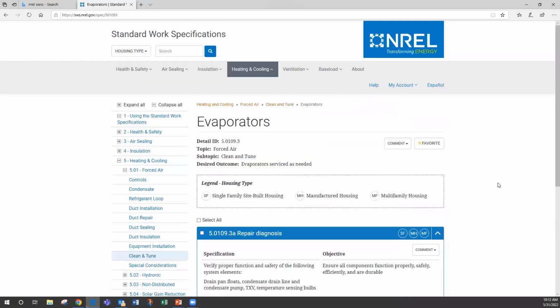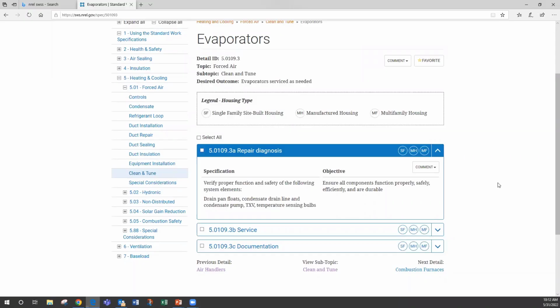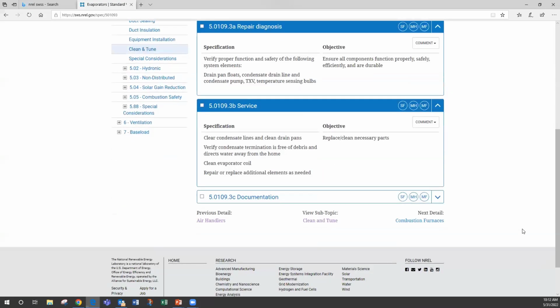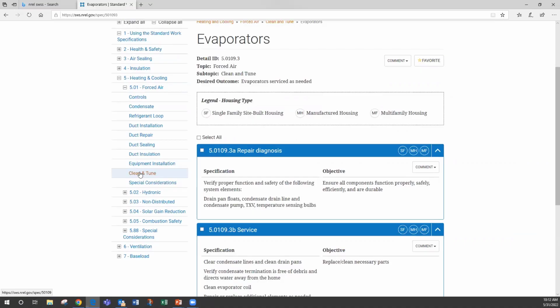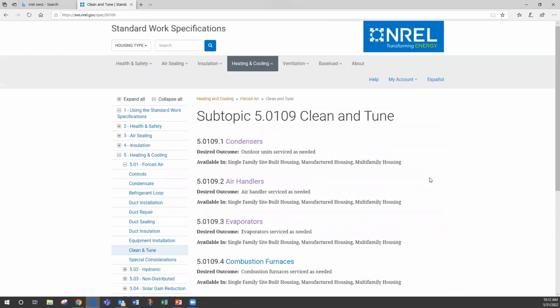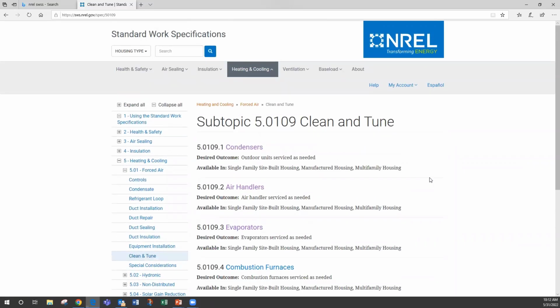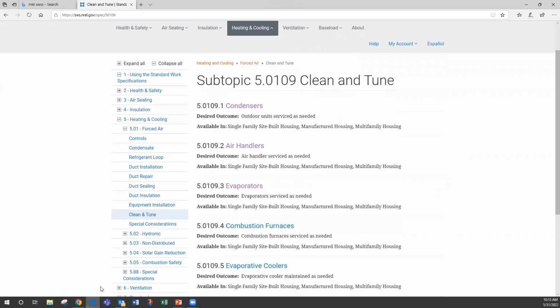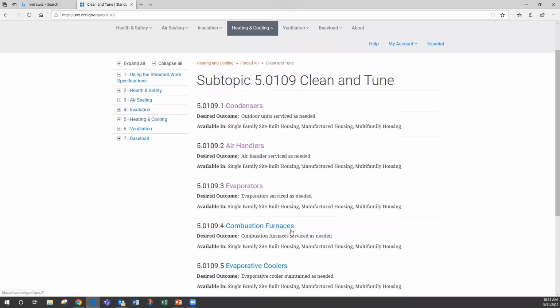Let's look at the evaporator, so that's the indoor coil. Proper function and safety: drain pan floats, condensate drain, condensate pump, TXV, that's your thermal expansion metering device, sensing bulbs. Service, clear condensate lines, clean drain pans, verify condensate terminations are free of debris and direct water away from the home, clean the evaporator coil, repair and replace additional elements as needed, and then the documentation piece. I know this should be routine for the HVAC contractors, but I want you to be aware of where you would find, if one of these jobs gets inspected and monitored, the desired outcome they'll be looking at to judge whether the job was done appropriately. Okay. So that's all under Section 5, heating and cooling.